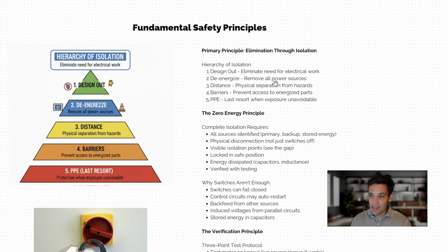The first way we do this is referred to as the hierarchy of isolation, where we want to design out the hazard. So for example, we want to actually eliminate the need for electrical work in the first place. Can we avoid doing any sort of live work? Can we energize the whole facility at the end of the project when no one's going to be working around live conductors? So that's designing out. The second principle is actually de-energizing before we do the work. So obviously we don't want to work around or near live power sources, so we remove the electricity.